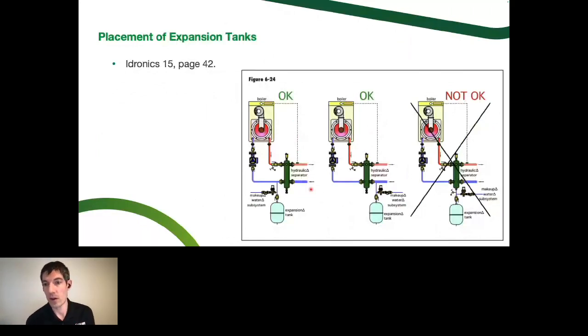So one of the next questions that we get is, where do we put the expansion tank? It's a little bit more straightforward with closely spaced tees. Like Dan Holohan says, we want to pump away from the expansion tank. So my book answer would be, let's put the expansion tank right on the inlet of the boiler circulator. We're pumping away from that, and we're going out to the system from there. So this is a good spot.